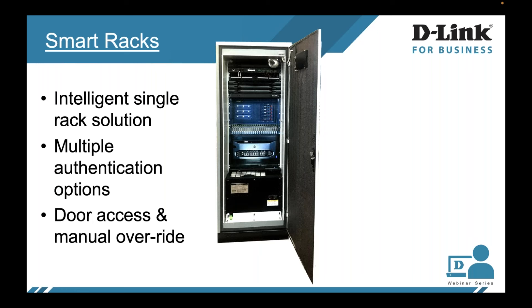Once cooling is taken care of, you want to know whether everything is all right. What you see on the door is an LCD panel — from outside you can see the temperature and humidity inside the rack. That's local visibility. Second, if you are not there, an IT manager wants to know what is happening at a remote location. With remote triggering, you can set a threshold — say 20 to 22 degrees — meaning the temperature should never go above 22 or below 20.